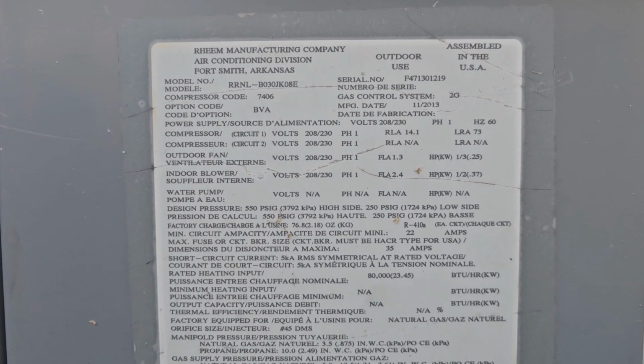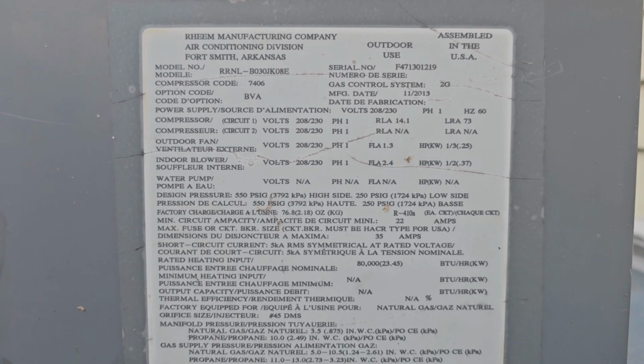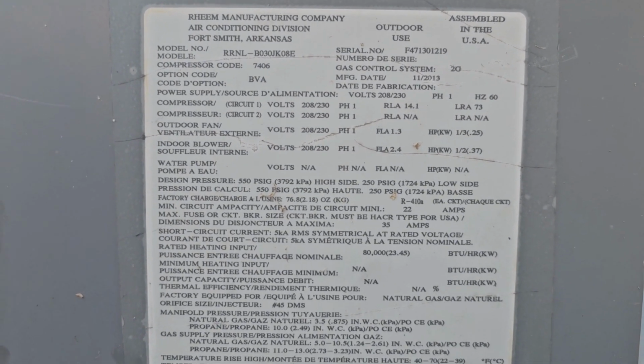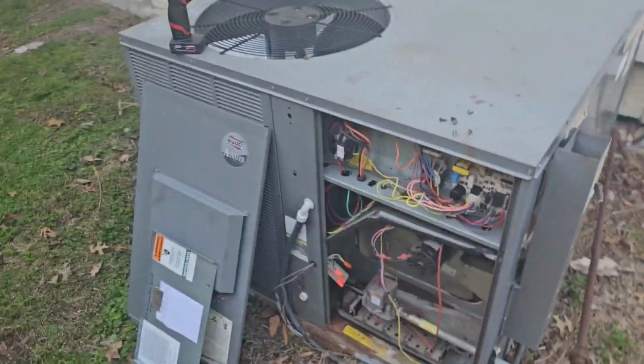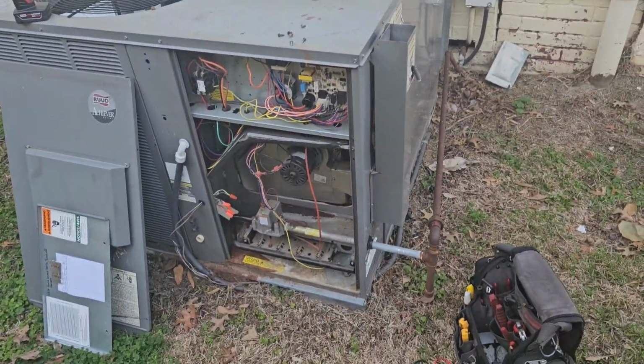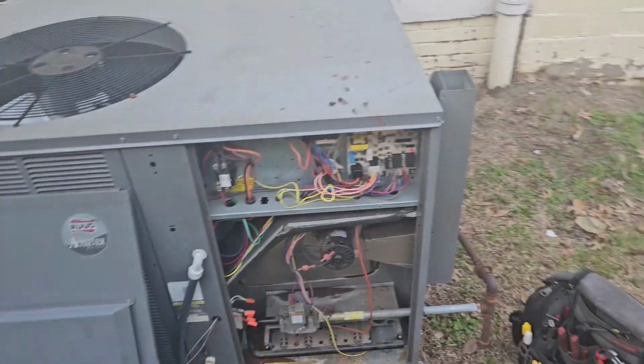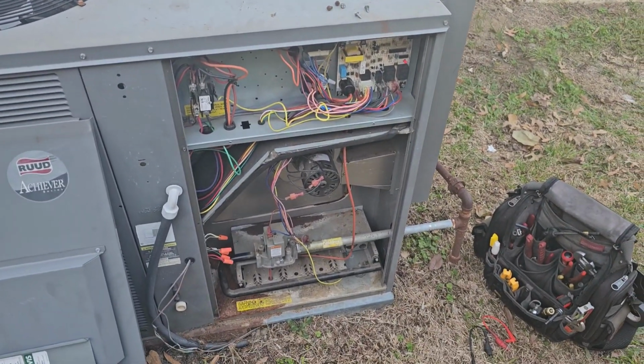So, 80,000 furnace or package unit, I believe that's why my Delta T is so large. And there's a crap ton of force coming out of all the vents. So even though the evaporator coil in there is slightly dirty, it's working well enough right now to maintain that first floor.